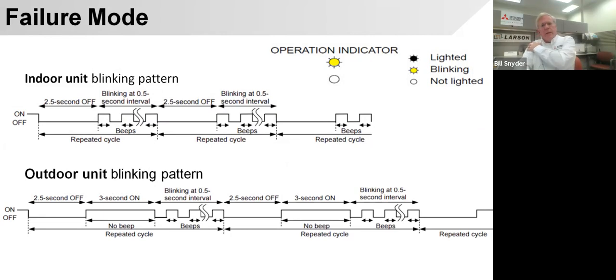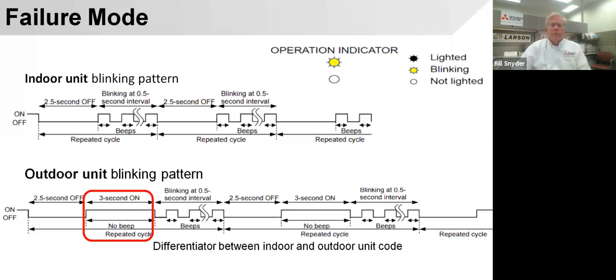Talk a little bit about troubleshooting. There's a blinking light on the indoor unit, typically if it's a wall unit, that shows up like this in the instructions. This is just telling you the blink interval. Pretty easy to tell that it blinks maybe 3 times and a pause, 3 times and a pause. Then we would go to the service fax and get that information.